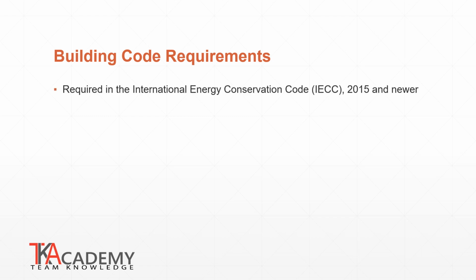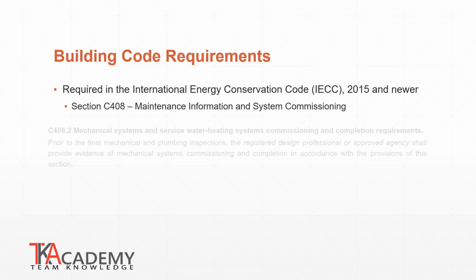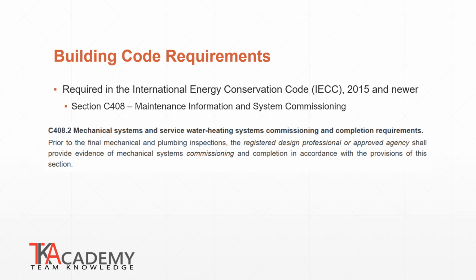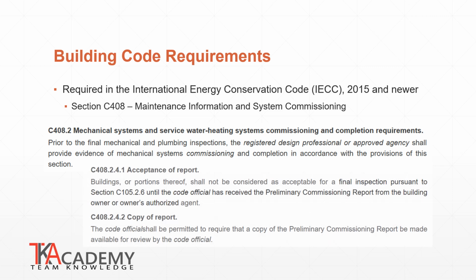As of 2015, the International Energy Conservation Code requires commissioning of basic systems in new buildings. At a minimum, the mechanical and water heating systems are to be commissioned prior to the final building inspection. The code states that buildings or portions thereof shall not be considered acceptable for final inspection until the code official has received and reviewed the commissioning report.